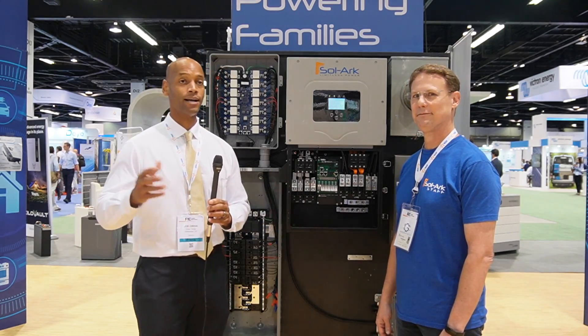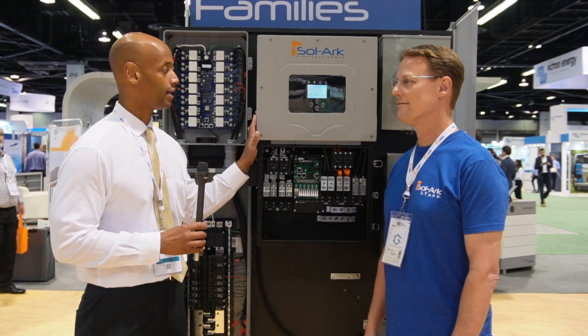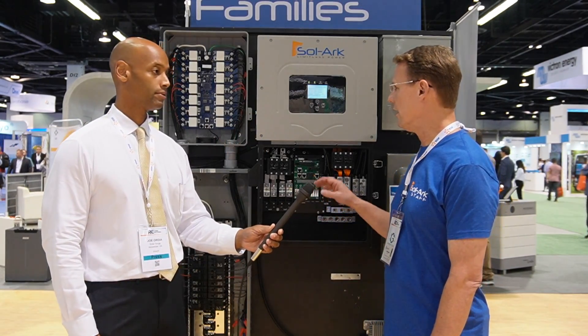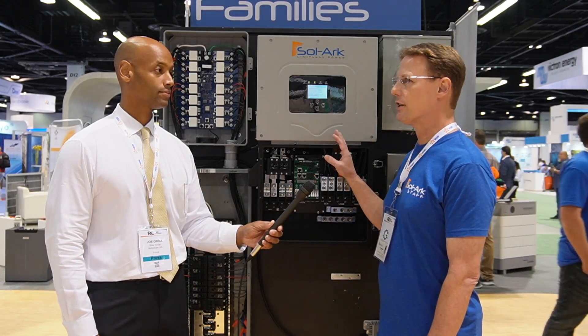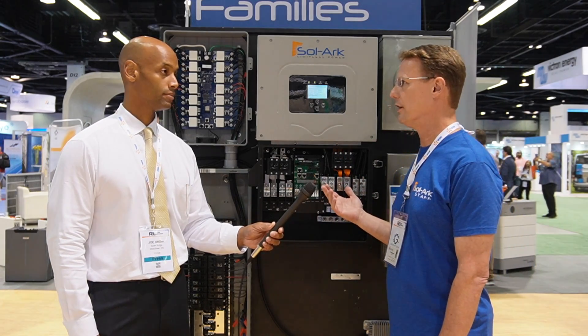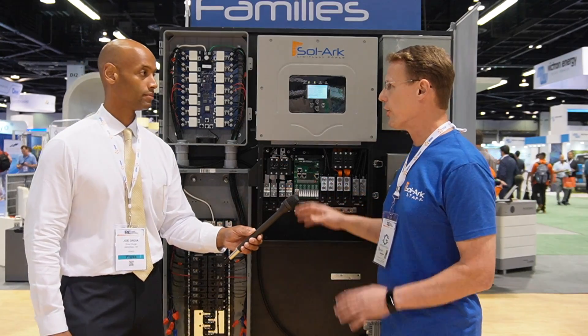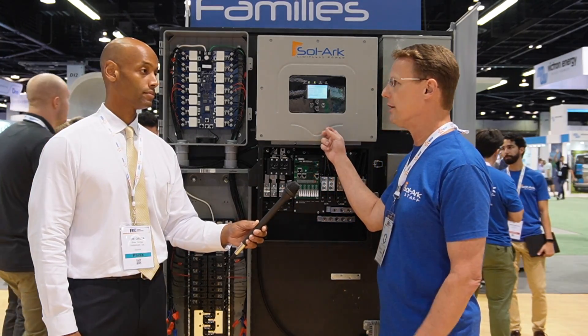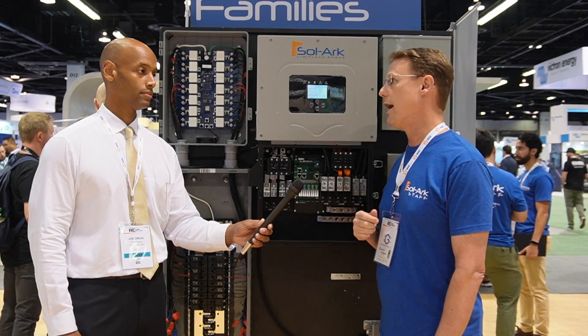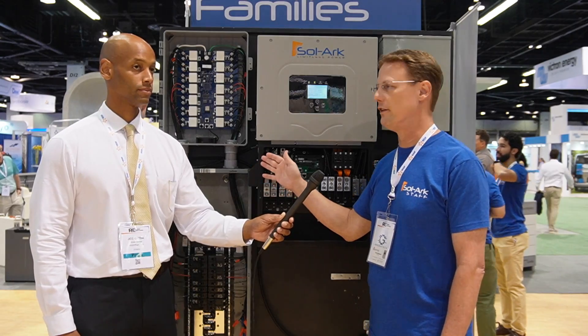This is an area that a lot of our viewers have been paying attention to — this idea of load control, load management, and visibility on what loads are drawing power within the home. Can you explain how having an intelligent load management system extends the capability of your solar and storage system? Well, a hybrid inverter along with batteries does a lot of things for you — a lot of backup power. However, it can be pricey; it costs about $2 a watt, not including installation. But when you add load management, you can manage the loads — not turn all the big stuff on simultaneously, but turn them on sequentially. The result is that you can double the effective power of the ESS at one-tenth the price per watt. It's the single biggest reduction in cost of anything on an ESS system.